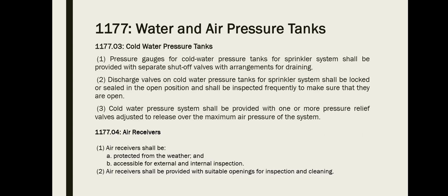Next is Rule 1177.03, cold water pressure tanks. First, pressure gauges for cold water pressure tanks for sprinkler systems shall be provided with separate shut-off valves with arrangement for draining. Then two, discharge valves on cold water pressure tanks for sprinkler systems shall be locked or sealed in the open position and shall be inspected frequently to make sure that they are open.